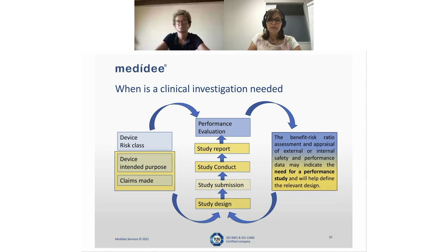Once you have identified whether there is a gap or not, based on the device's intended purpose, the claims which are made, and, for example, the state-of-the-art identified as part of your performance evaluation, you will be able to design the study that you will need to perform, and then afterwards conduct your study in order to feed the results of your study back into the performance evaluation. So this is really an ongoing process within the entire life cycle of your device, and is the starting point to illustrate whether or not more clinical data are actually needed.